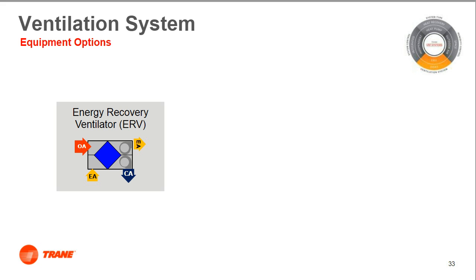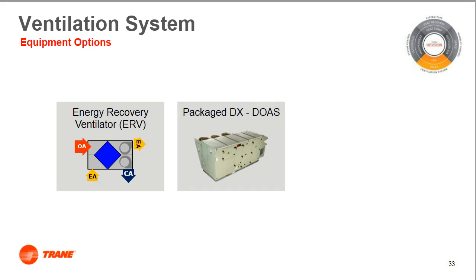Conversely, a dedicated outdoor air system uses a cooling and heating coil to condition the outside air to a specified set of conditions. This allows the ventilation air to be adequately dehumidified without relying upon the VRF terminal units to offset some of the ventilation load. The dedicated outdoor air systems are often standalone, air-cooled DX units, or a package unit. Or some might be split systems featuring a VRF coil connected to a VRF system with a linear expansion device, as we saw in earlier slides.